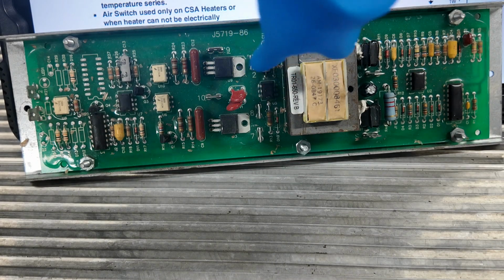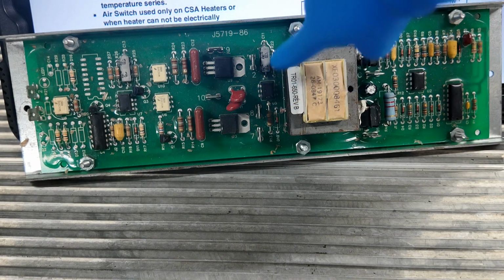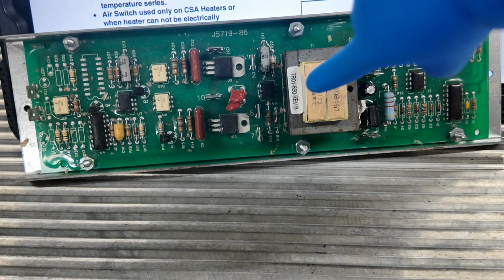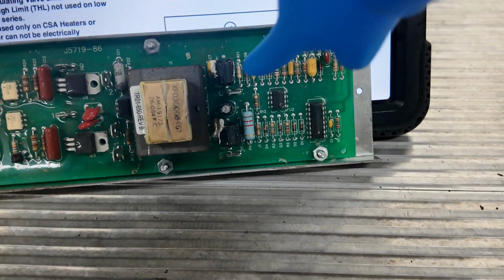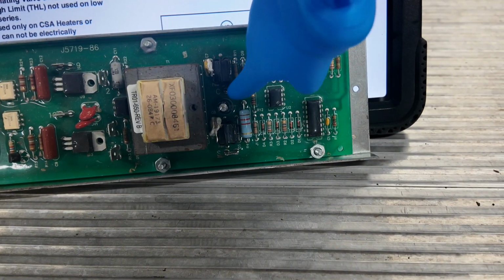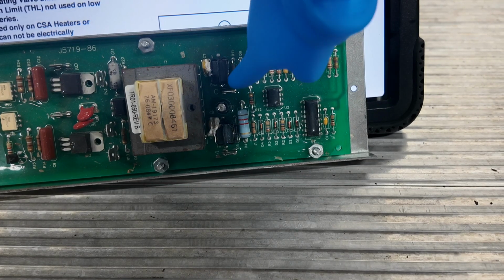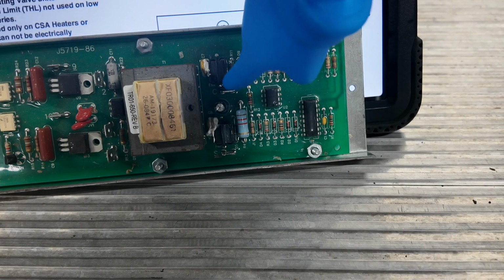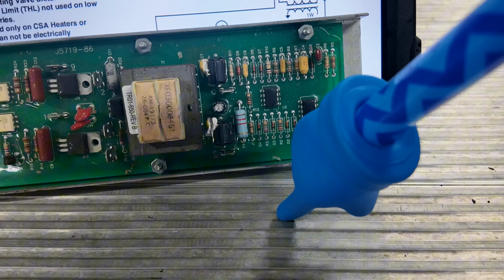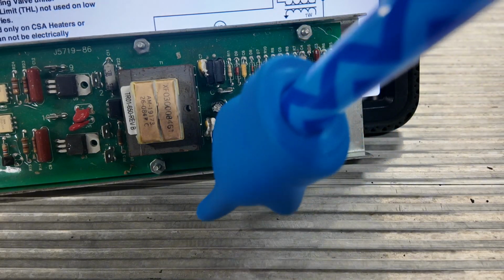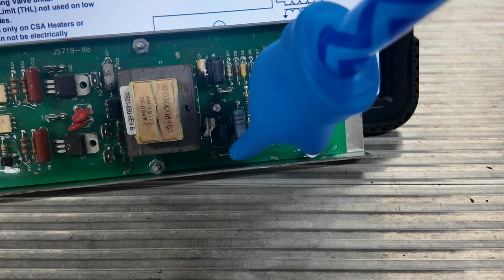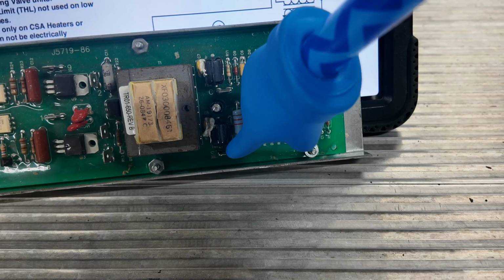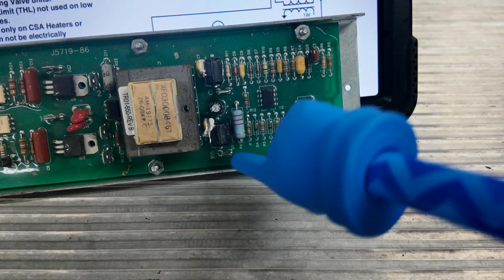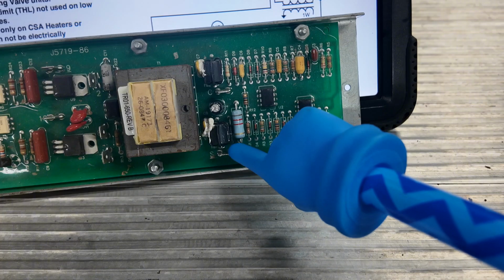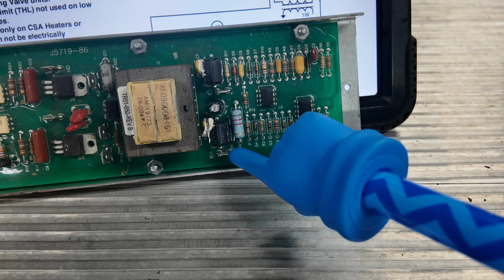So this board is fairly universal because of the way that's controlled. I've used this board for a few different applications. Come over here, we have common right here. That is the terminal that would connect to burner ground. I would normally connect that in the bottom of the box and then have a wire from there going down to your burner to ground your actual burner. Right here, you have your S terminal on this board. That is your flame sensor.